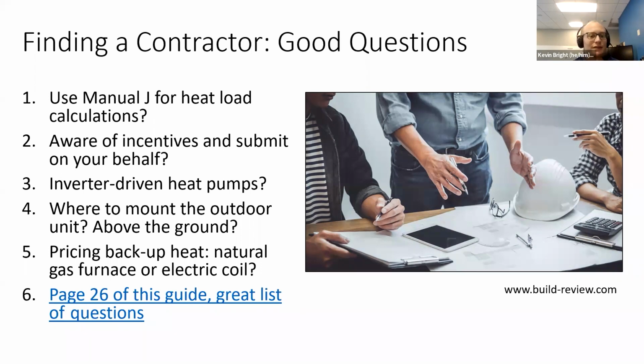And then the last part on here is a pretty important one too, thinking about backup heat. So heat pumps work in Minnesota. Some work down to minus 14 degrees or minus 20 degrees. And then there are models that really are only functional to outdoor air temperatures of 5 degrees or 10 degrees above zero. So in some cases, or in many cases, you'll need to think about what that backup heat is for when outside air temperatures perhaps fall below minus 15 or fall below 5 degrees or 10 degrees.